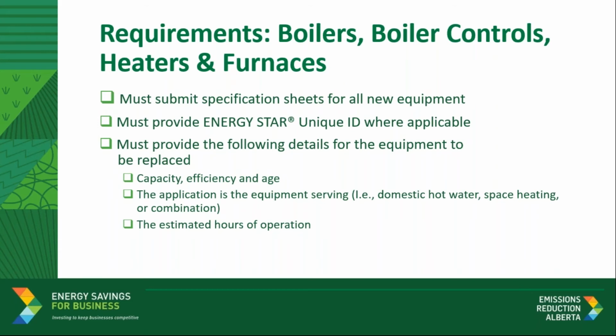And when applying for the incentives, you will have to submit the specification sheets for all of the new equipment. You must also provide information that is included on the nameplate of the existing equipment, and that includes capacity, efficiency, and age. You would need to also provide the specific application that the equipment is serving. For example, if it's a boiler serving domestic hot water or space heating, or is it both? So you would need to specify that. And lastly, you must also provide an estimate of the annual hours of operation.